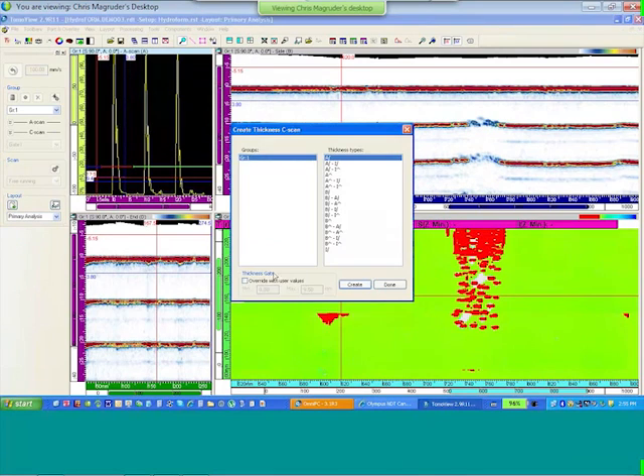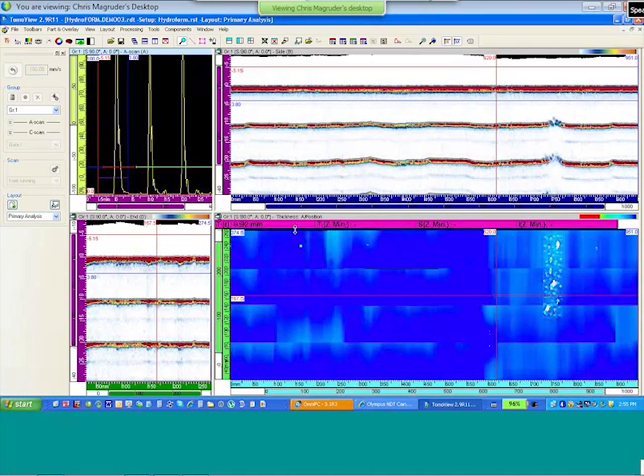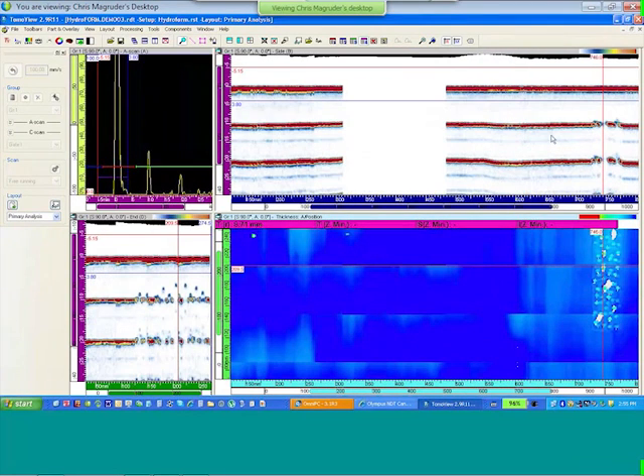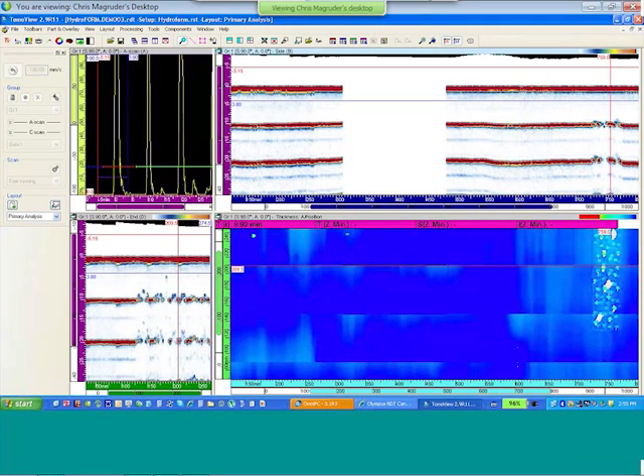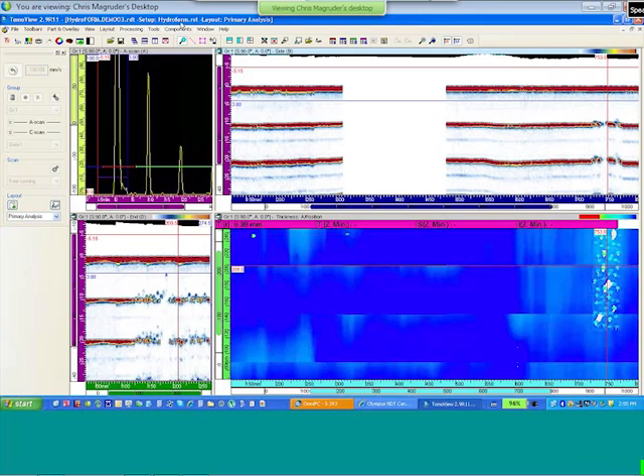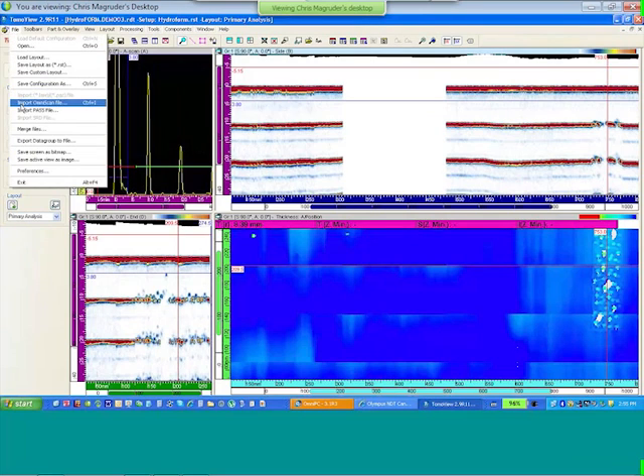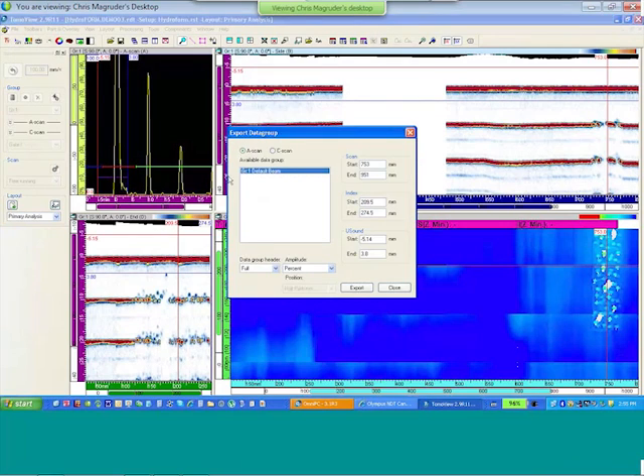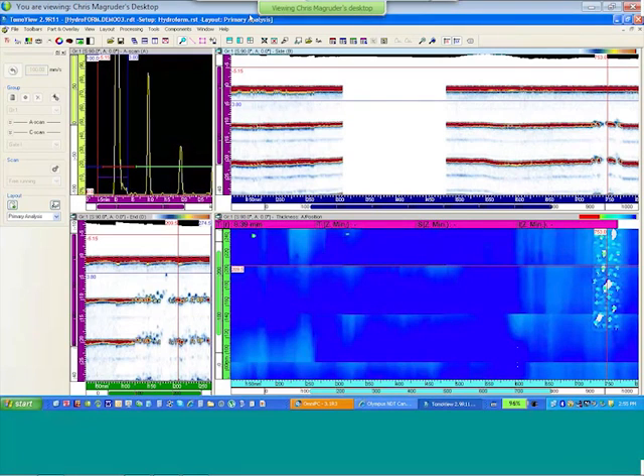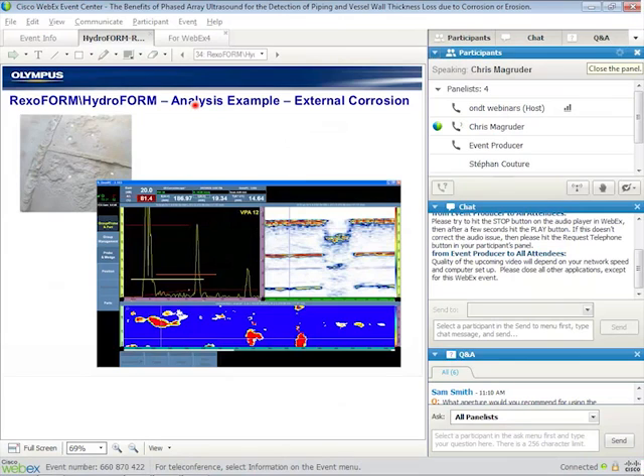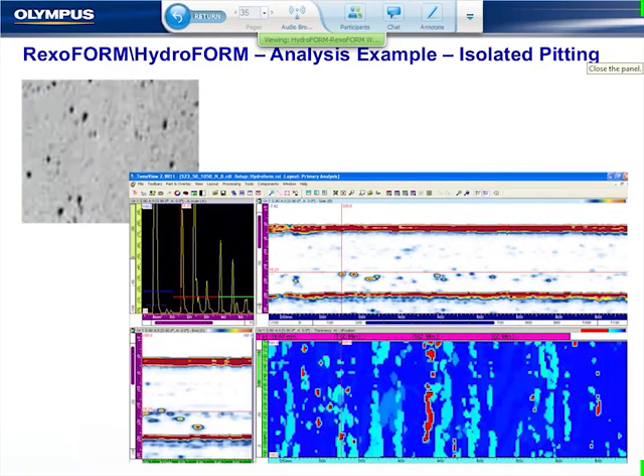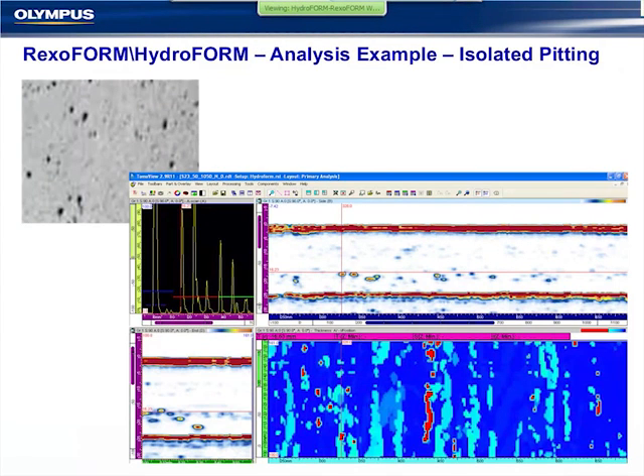In the offline analysis now, we can create a customized C-scan and perform analysis with a similar set of tools for zones and the minimum thickness. I can see the B-scan and D-scan simultaneously. And it has an output function so that we can export the data file, either the A-scan or C-scan, to a third-party external analysis program similar to Technical Toolbox or one of the other commercially available systems.